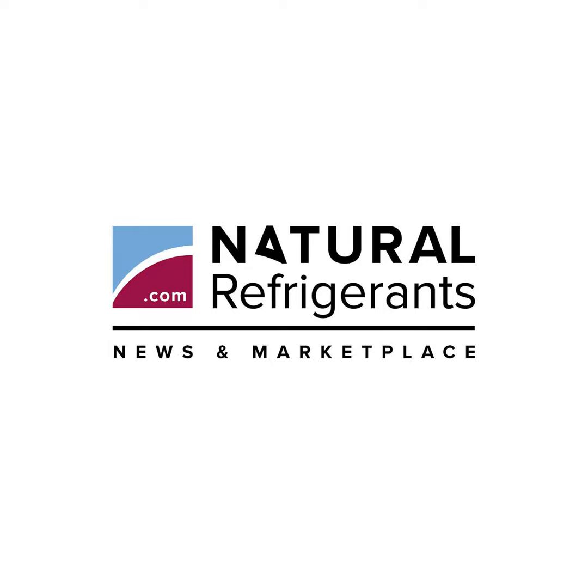What benefits does the technology offer? What market conditions factor into it? Our technology is not a heat pump competitor, but a synergistic hybrid solution. Heat pumps operate efficiently at 40 degrees Fahrenheit, 4 degrees Celsius, but as it gets colder, COPs go down. Meeting the coldest ambient temperature heat loads requires exponentially bigger heat pumps, with only a third of the unit's capacity used in 90% of its operation. In Europe, the electrical connection price is based on the heat pump's capacity. We cut that peak off. By sizing the heat pump for the capacity used 90% of the time, we lower capex per kilowatt, while our hydrogen technology handles the coldest days.